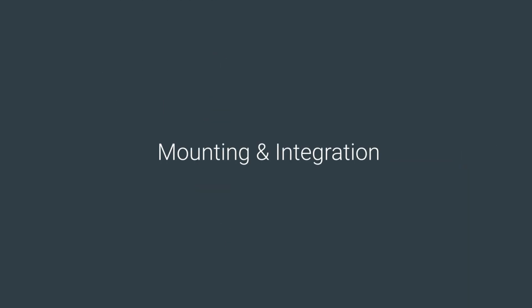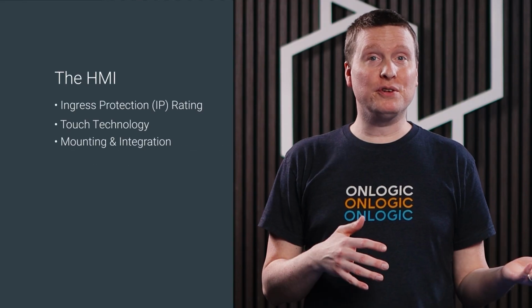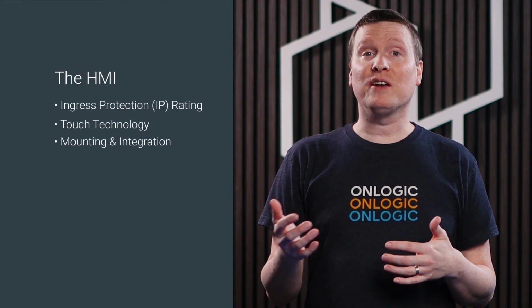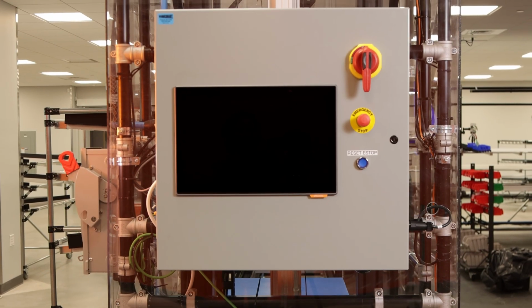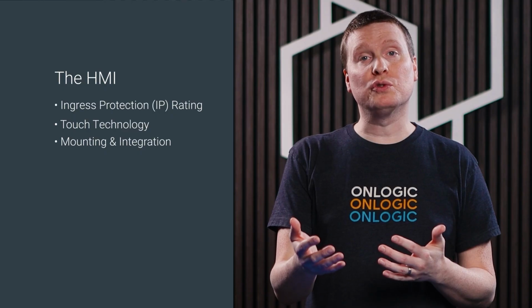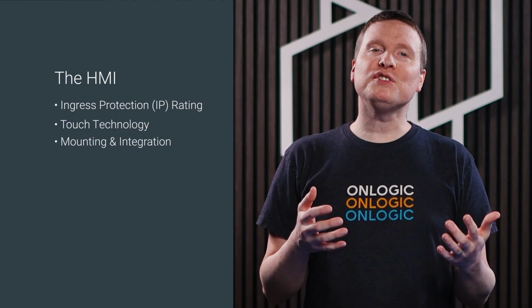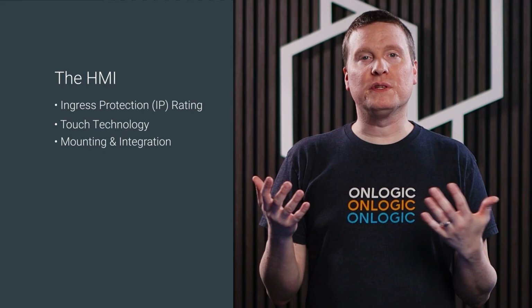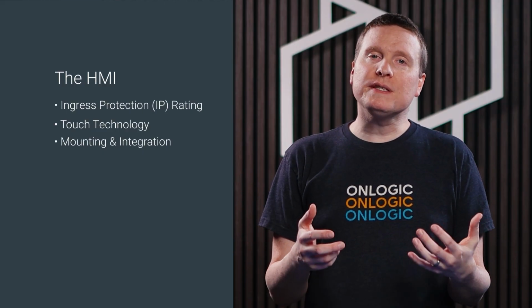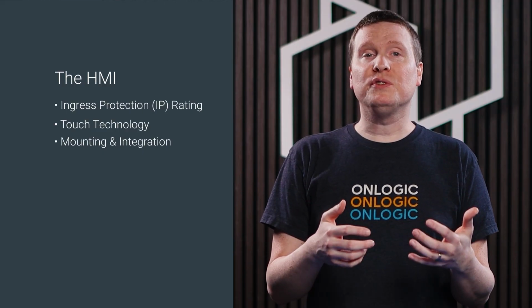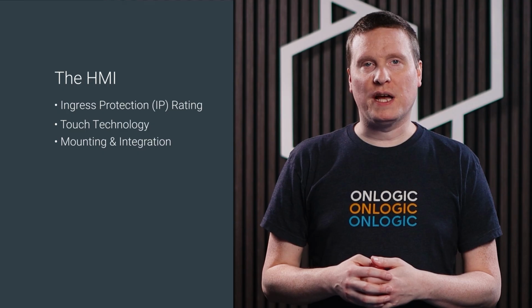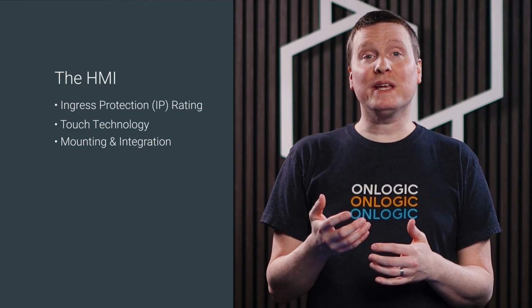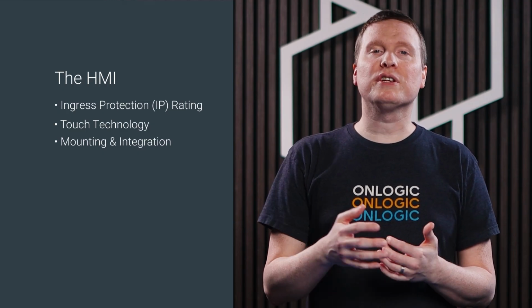Finally, there's mounting and integration. How will the touchscreen fit into your facility? Look for VESA or panel mount options that allow for a seamless flush installation into existing control enclosures or swing arms. The space you have to mount will often inform the size of the screen, so make sure to consider where it will go and what it will need to display before settling on a screen size. Lastly, if your environment gets a lot of direct sunlight, be sure to consider the maximum brightness of the display.